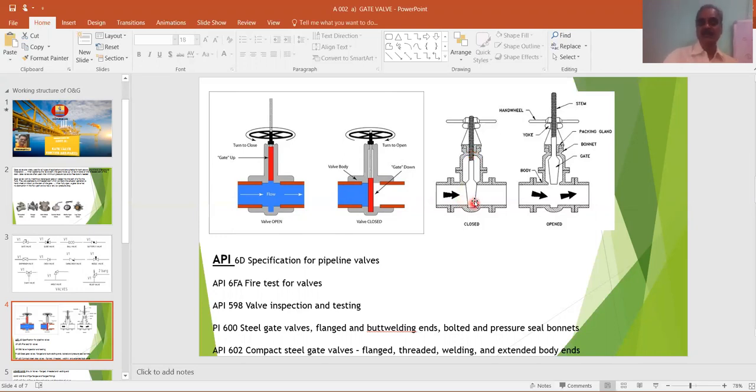When you are replacing or repairing these internals, it should be retested. Upstream test, downstream test and seat leakage test as per API 598.